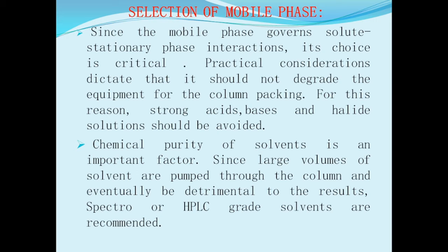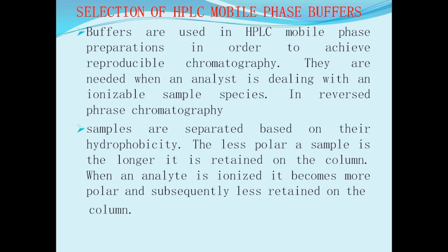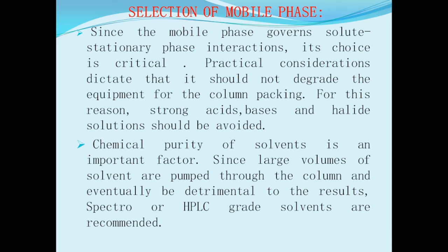Spectro or HPLC grade solvents are recommended. Volatility should be considered if sample recovery is required. Viscosity should be less than 0.5 centipoise, otherwise higher pump pressure is required and mass transfer between solvent and stationary phase will be reduced.